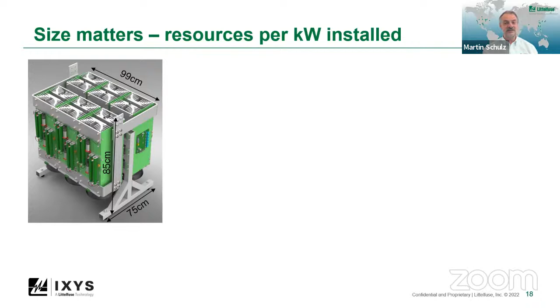And here is a schematic, a scheme drawn to scale. If you achieve 97% efficiency on a solution handling megawatts, you need to get rid of a lot of power. So the losses in these gray blocks stack up to 60 kilowatts.